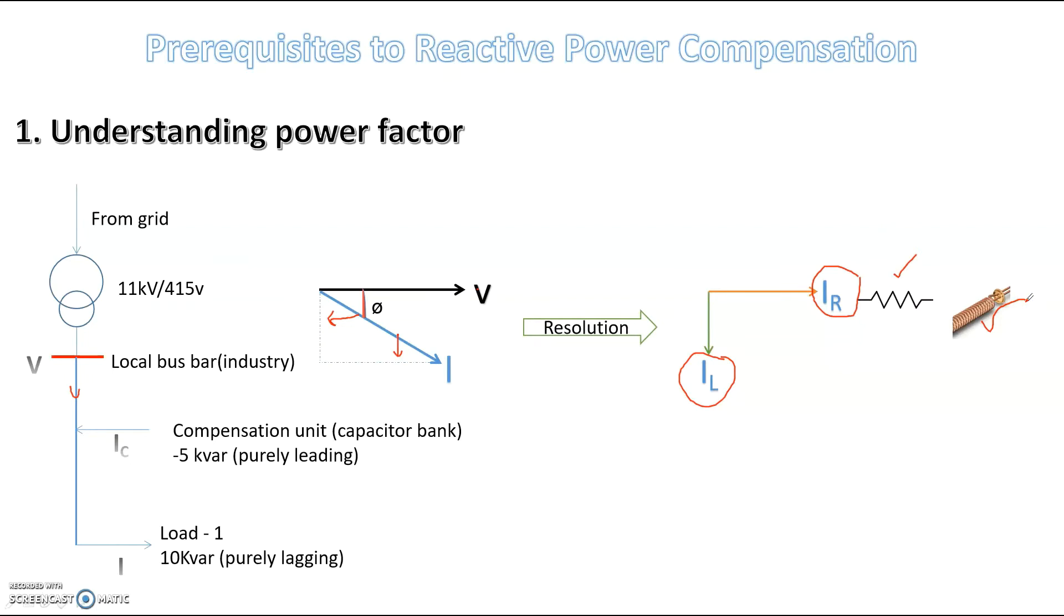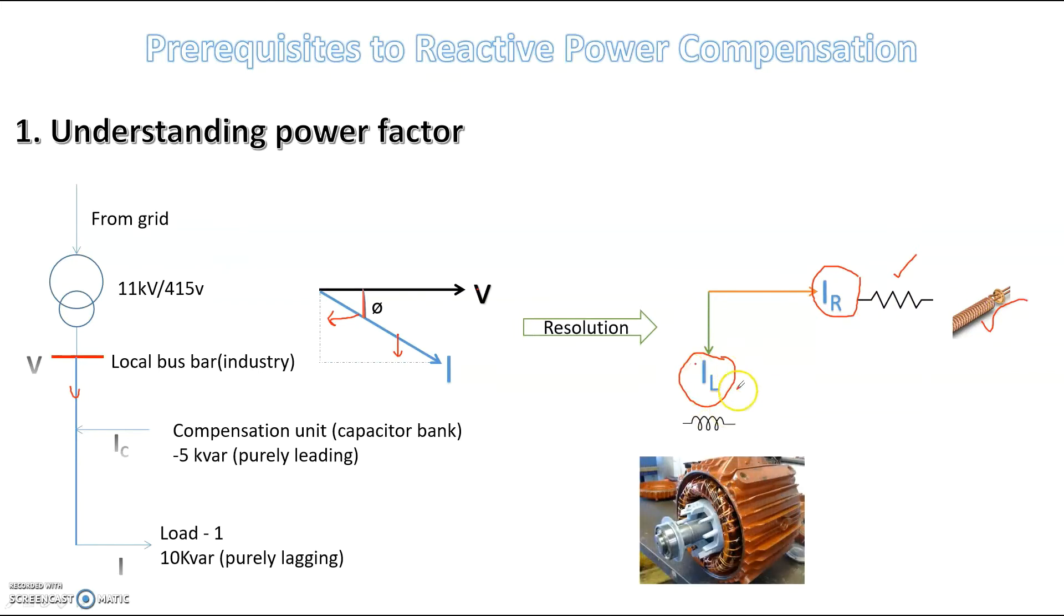This current is basically resistance and resistors are basically the heater elements, the heater elements which are going to cause the heating loss. Now, this inductive component, from where does this inductive component come? The industries have huge motors, and these motors will be having these windings. These windings are basically a lot of coils, and those coils are basically producing the magnetic field. To produce the magnetic field will be requiring the reactive power or a component of the current which is 90 degree out of phase by the voltage. So this inductive current comes from these large industrial motors.